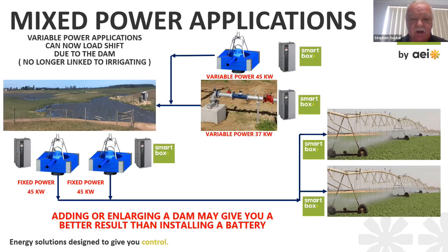In this project, one of the key things we've done is provide a mixture of power applications — we changed some of the fixed power applications to variable power applications. Now the river pump only pumps to the dam, the bore pump only pumps to the dam, and 2 new floating pumps were installed on the dam that now pump to the pivots. They are all fitted with variable speed drives.